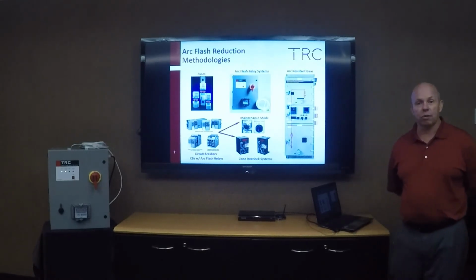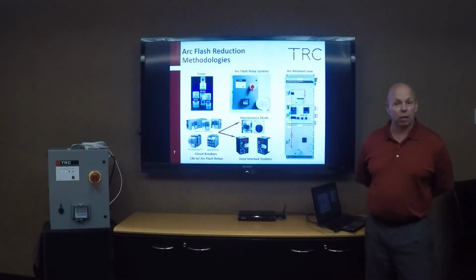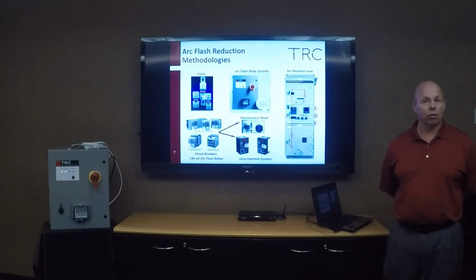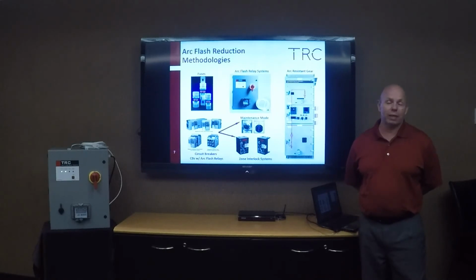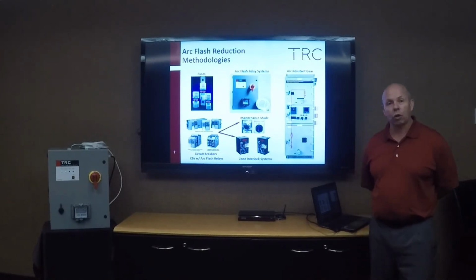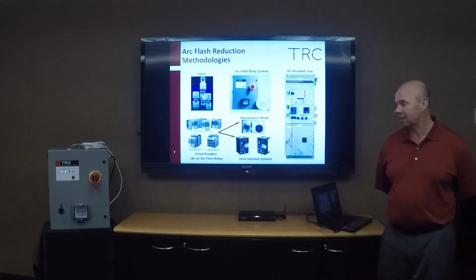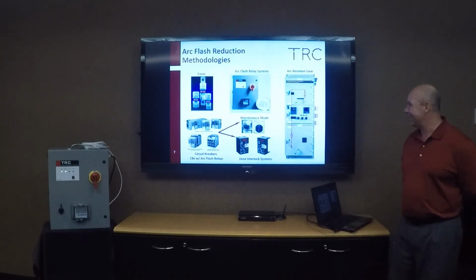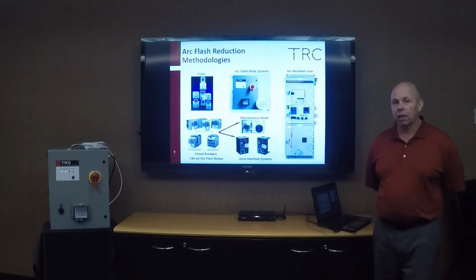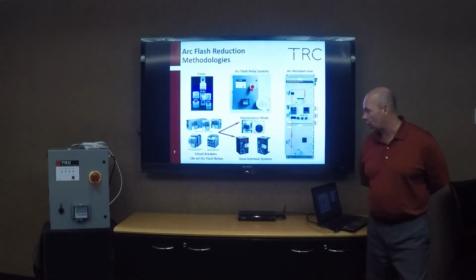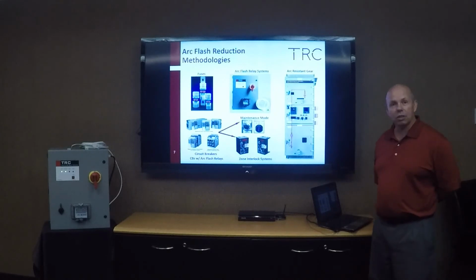Circuit breakers also come with arc flash relays built into them. There are a few manufacturers, Schweitzer, ABB, General Electric, that have arc flash relays that go into the switchgear power breakers, whether they're low voltage or medium voltage. These are good devices that you can use. Most of them are current-driven devices, so that when they detect an arc flash through overcurrent, more along the lines of the short or arcing current, then it will trip the breakers and remove power from the system. Another method that has been commonly used is arc-resistant gear. Arc-resistant gear includes some types of overcurrent protective devices, whether it's zone interlocking or established arc flash relays within the switchgear itself. A new technology that's been out for approximately 5 years now is an external arc flash relay.